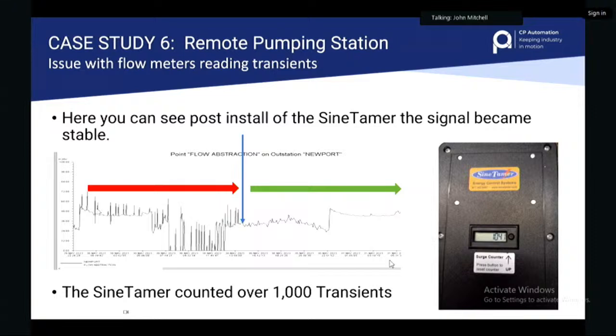This is their analog signal into their PLC system, and you can see these spikes on the signals here. This is the point we installed the SineTamer, on this date at roughly that time, just after 2 o'clock. Immediately, we started getting a normal response from the signal from the sensor. So this SineTamer was not put on the sensor signal. It was put on the main supply of the incomer to that panel, and it cleared up everything inside the panel. It's worked seamlessly, and that's been in there well over 3 years with no problem since.